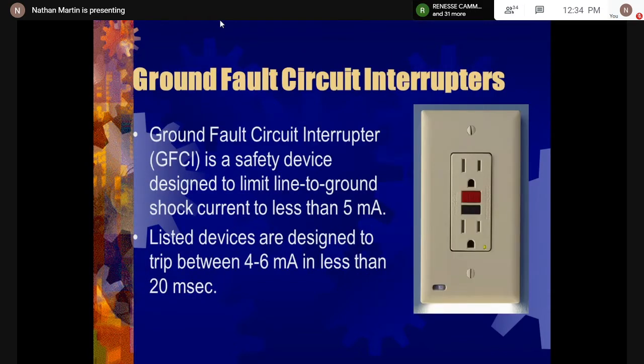The GFCI again, a better picture this week, and we're going to look at the device itself. These devices basically are designed to limit line to ground shock current to less than 5 milliamps. So between 4 and 6 milliamps, the device will trip in less than 20 milliseconds—very fast—before the current level can become dangerous.